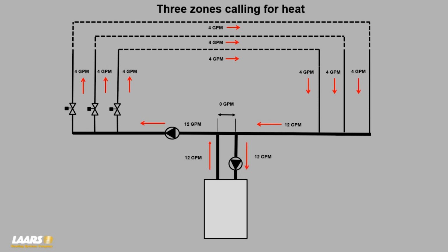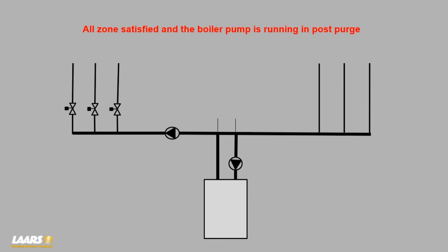Now, at the end of a cycle, and right now I'm showing 3 zones calling. Now let's say we're down to 2. Now we're down to 1, and we've satisfied the home or the dwelling. What happens? Do we shut the pump off? No. There's something called pump post-purge. And all you're going to do is just rat race that water out of the heat exchanger for about a minute. That time's adjustable. Most manufacturers have a pump post-purge, and that's what it is.